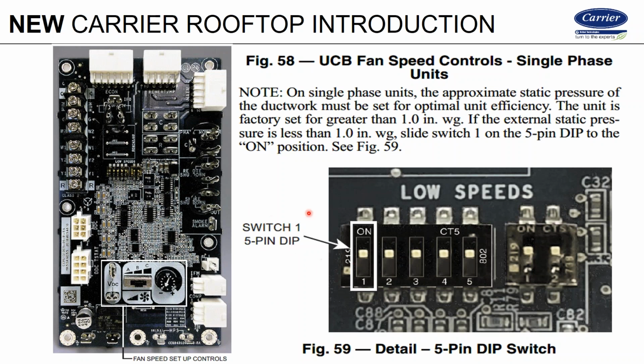This dip switch is going to toggle you between an inch of water column external static pressure or less. As this says here, if the external static pressure is less than an inch water column, then you want to slide switch 1 to the on position. Okay. If we have just the 2 dip switches on the 3-phase, it's a similar thing. We do the same thing, and we'll catch the detail on that too.